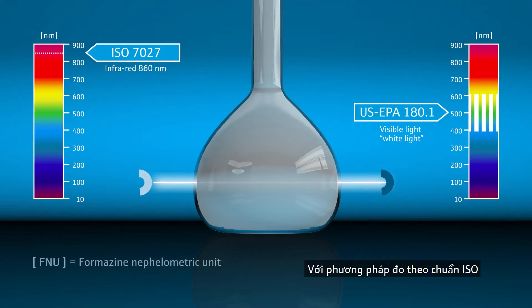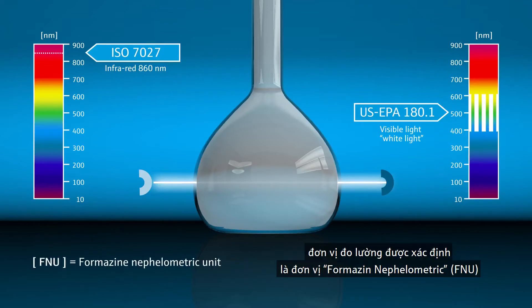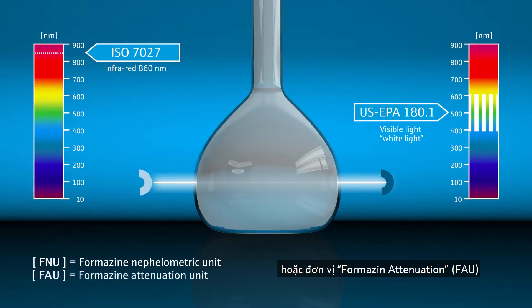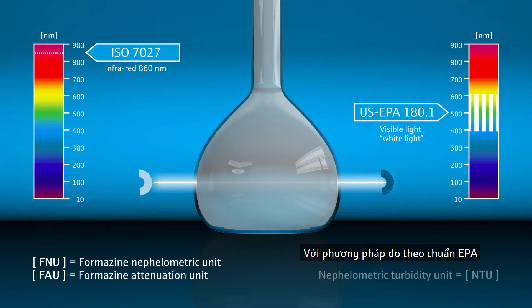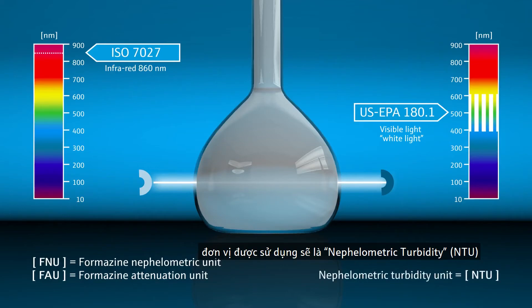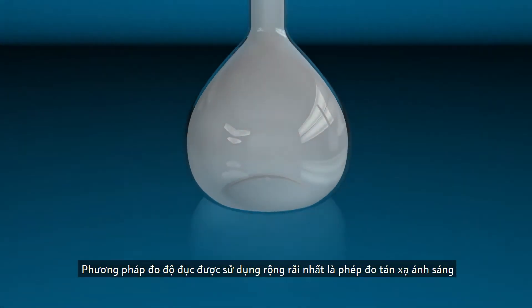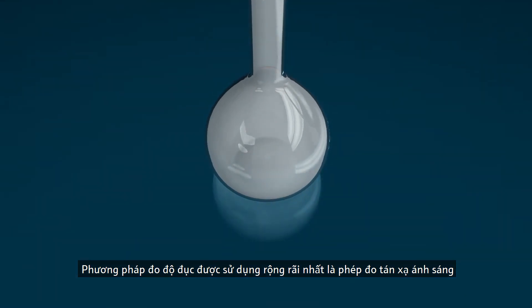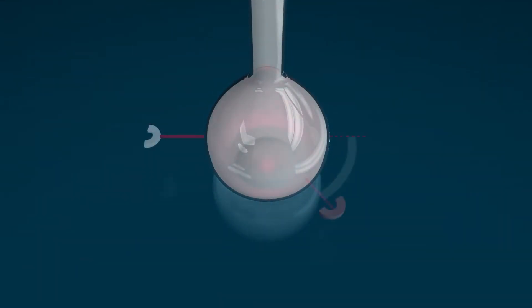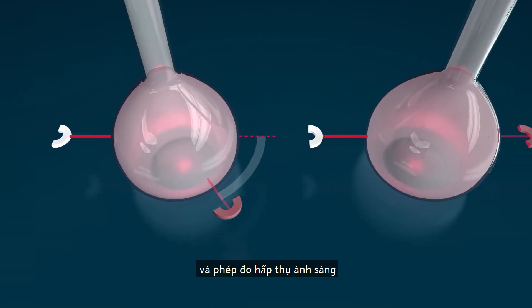For measurement according to ISO, the defined units are Formazine Nephelometric Unit (FNU) or Formazine Attenuation Unit (FAU). For measurement according to EPA, the unit is Nephelometric Turbidity Unit (NTU). The most widely used measurement methods for turbidity are scattered light measurement and attenuation measurement.